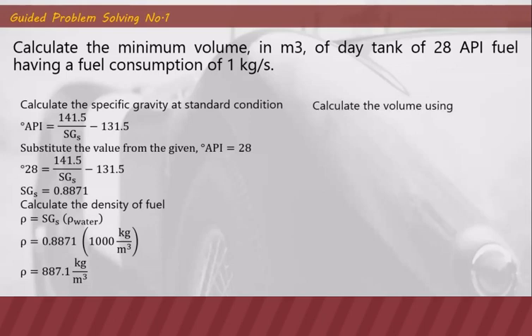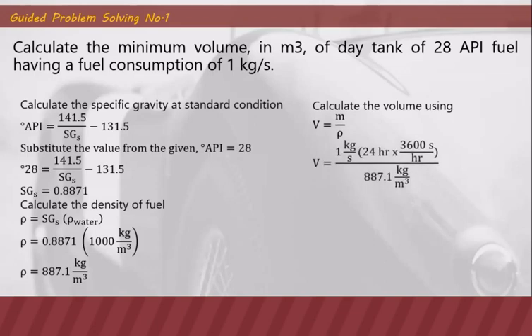We calculate the volume using the density-mass-volume formula: volume equals mass over density. Since the consumption is one kilogram per second and this is a day tank supplying for 24 hours, we convert to total kilograms by multiplying by 24 hours times 3600 seconds per hour, then divide by the density. The minimum volume for the day tank is 97.40 cubic meters — quite a large container.